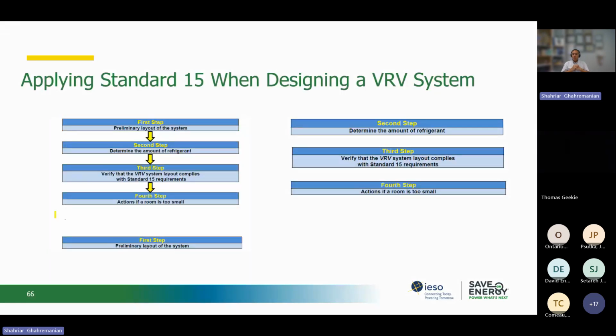And ASHRAE standard 15, when we are going to design a VRF system, basically says that we need to take these steps. First, we need to check the layout of the system, and then find the amount of refrigerant that needs to be charged to the system, and then verify the VRF system layout is compliant with ASHRAE standard 15. Then we go room by room and see that if a room is too small, maybe we cannot bring the refrigerant to that room actually. So again, this is really important to comply with the ASHRAE standard if we are going to consider a variable refrigerant flow system actually.